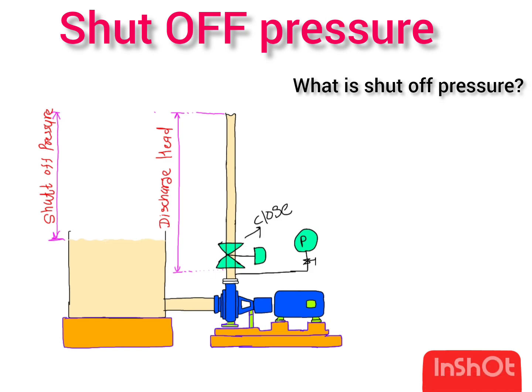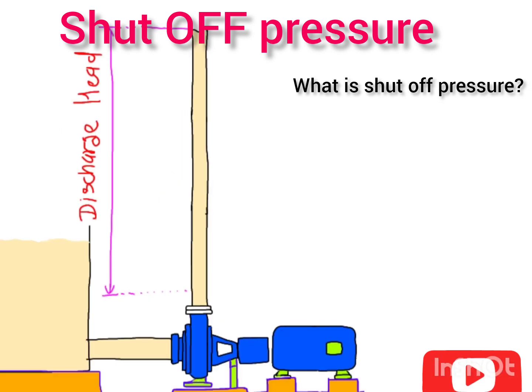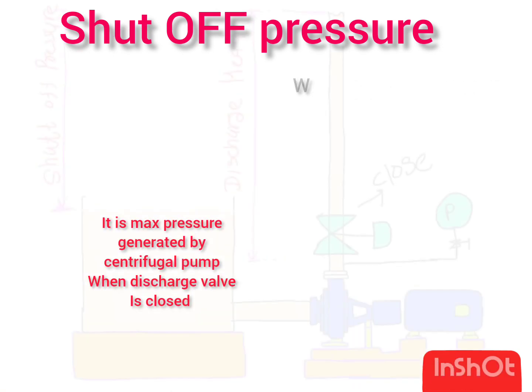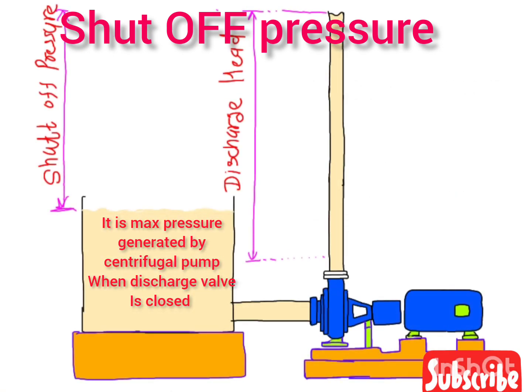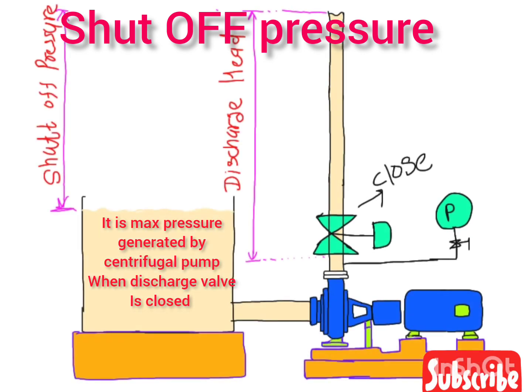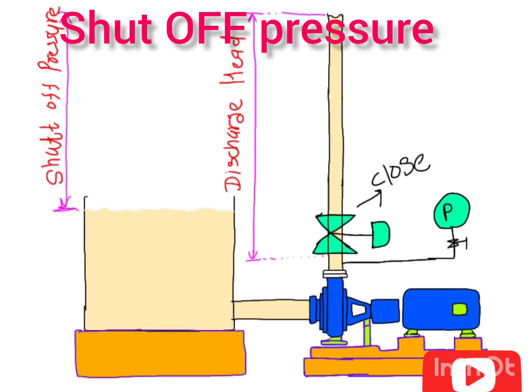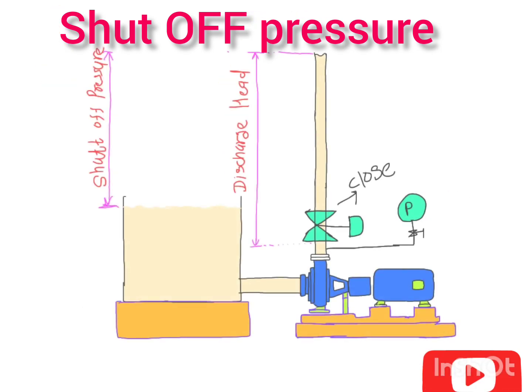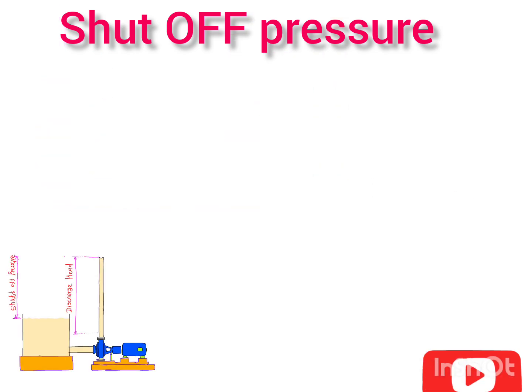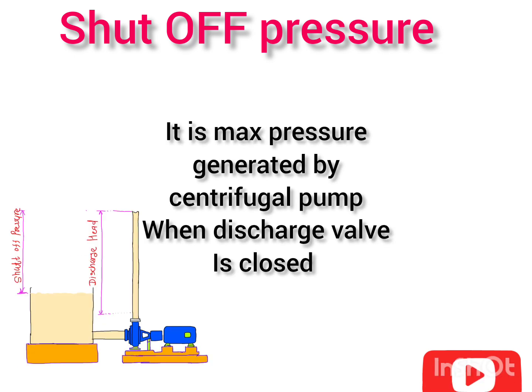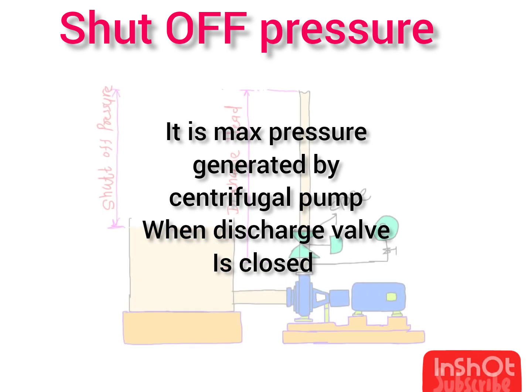So what is shut-off pressure in a centrifugal pump? The shut-off pressure is nothing but the maximum pressure that a centrifugal pump can generate when the discharge valve is closed. When the discharge valve is closed and there is no flow passing through the pump, the maximum pressure the pump can generate is called the shut-off pressure.